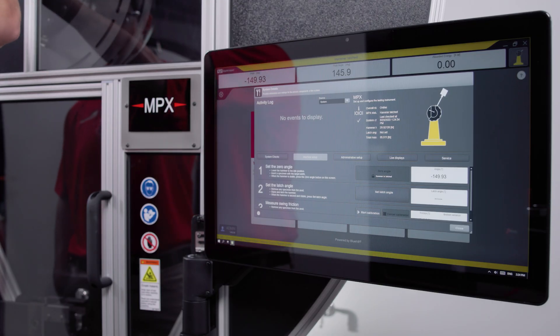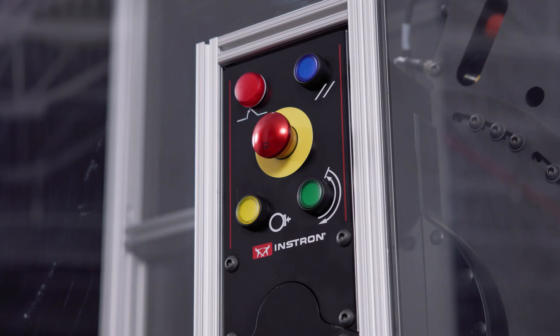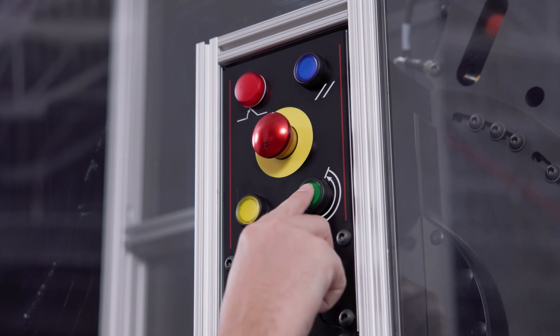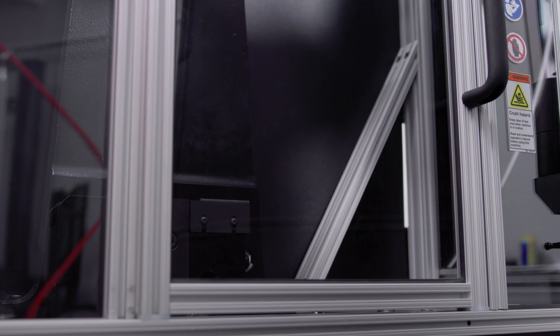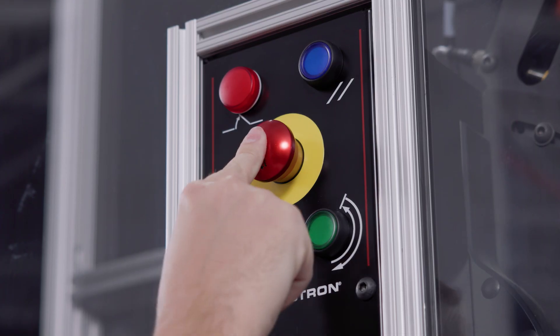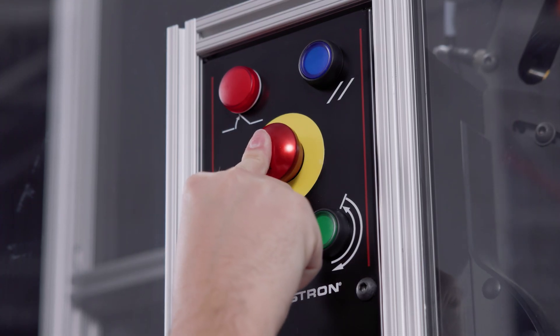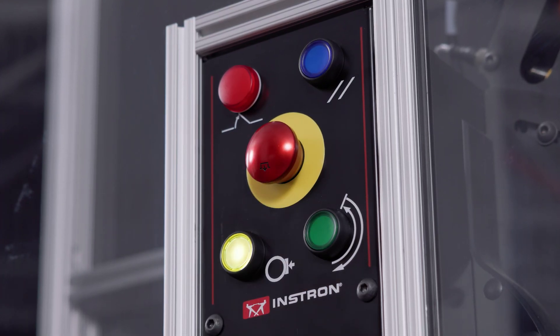If you do need to access these side areas, there are a few additional safety checks. First, we need to bring the hammer down to the zero energy position. You do this by pressing the green button on the control panel, followed quickly by the yellow button, which activates the system's brakes. Then, we press the red e-stop button, which is our emergency stop control. This button is used whenever you need to completely disable the system.